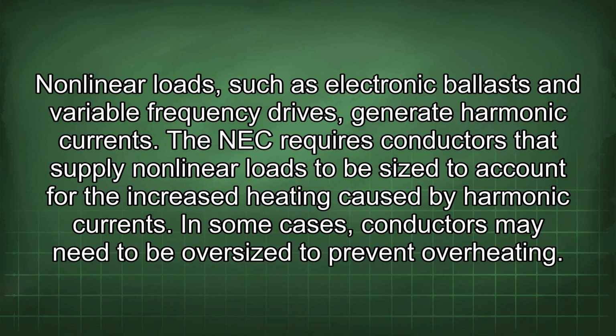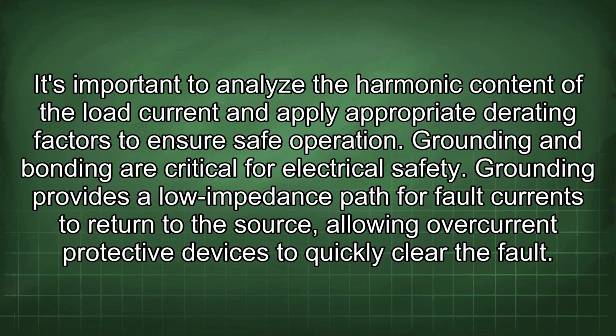The NEC requires conductors that supply nonlinear loads to be sized to account for the increased heating caused by harmonic currents. In some cases, conductors may need to be oversized to prevent overheating. It's important to analyze the harmonic content of the load current and apply appropriate derating factors to ensure safe operation.